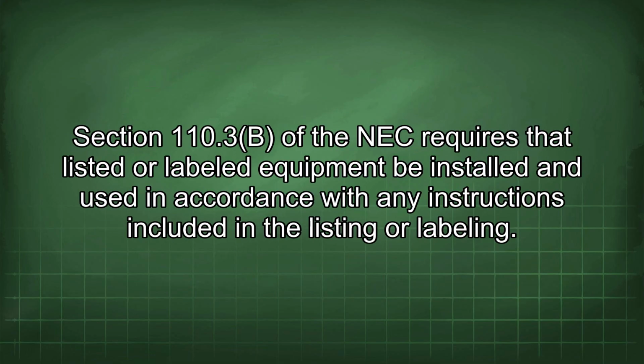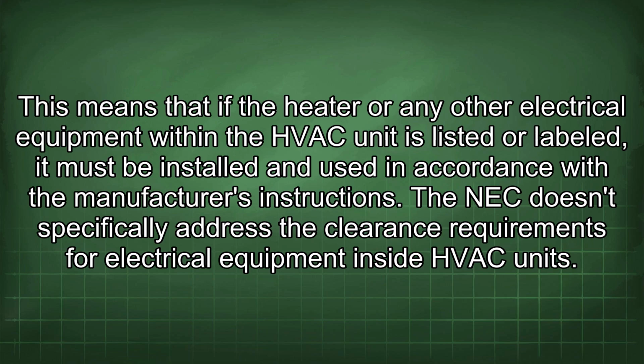Section 110.3(B) of the NEC requires that listed or labeled equipment be installed and used in accordance with any instructions included in the listing or labeling. This means that if the heater or any other electrical equipment within the HVAC unit is listed or labeled, it must be installed and used in accordance with the manufacturer's instructions.